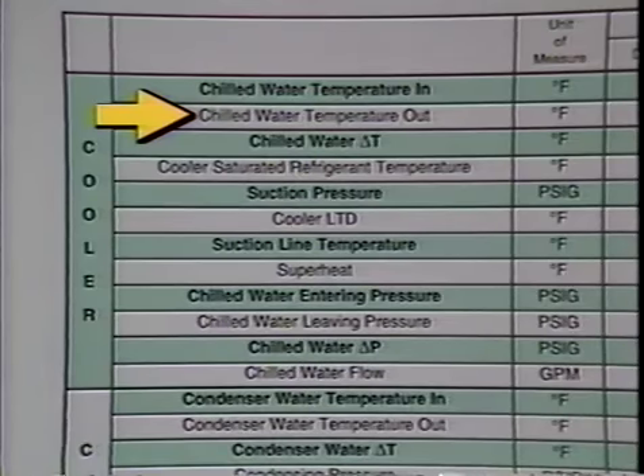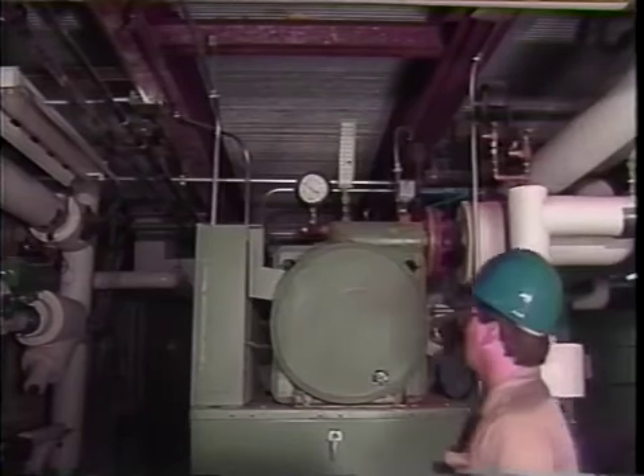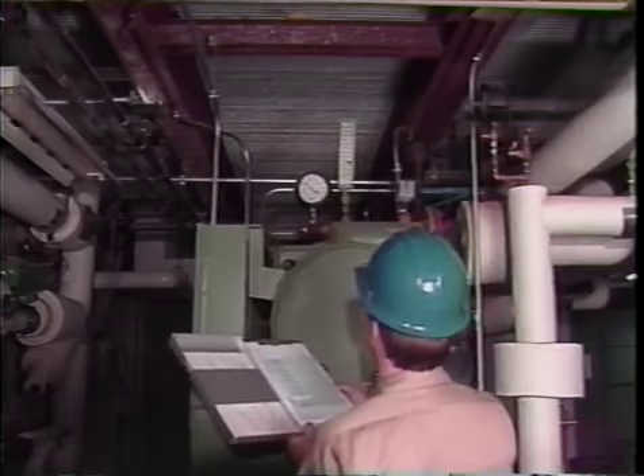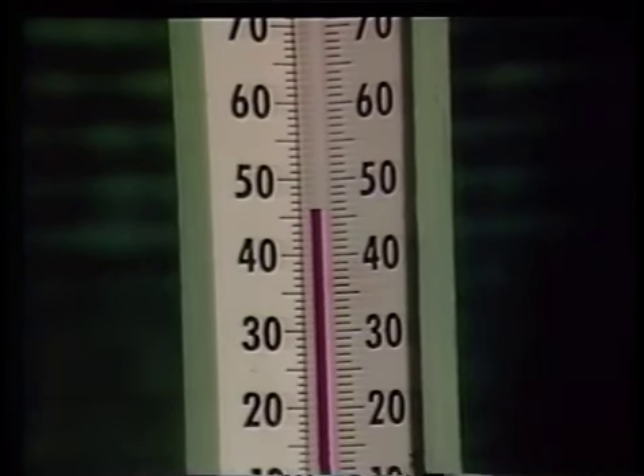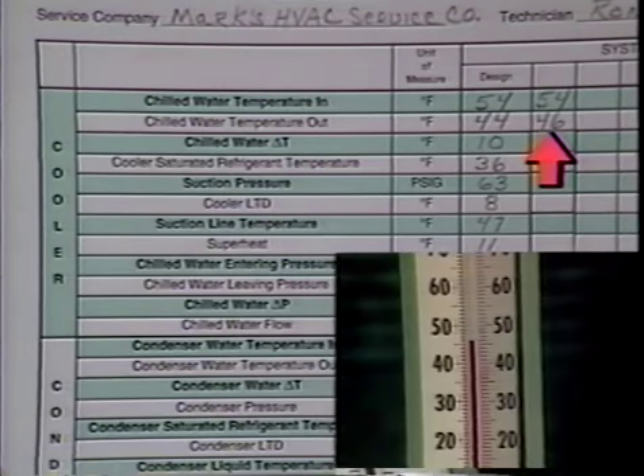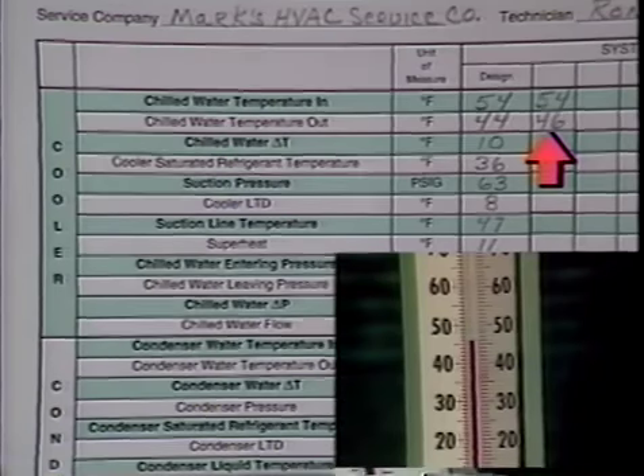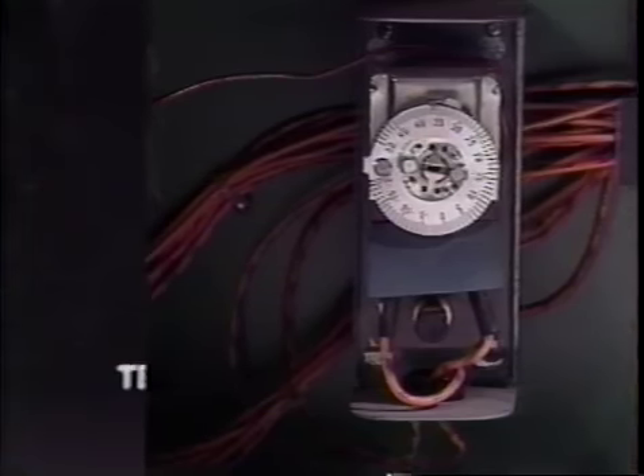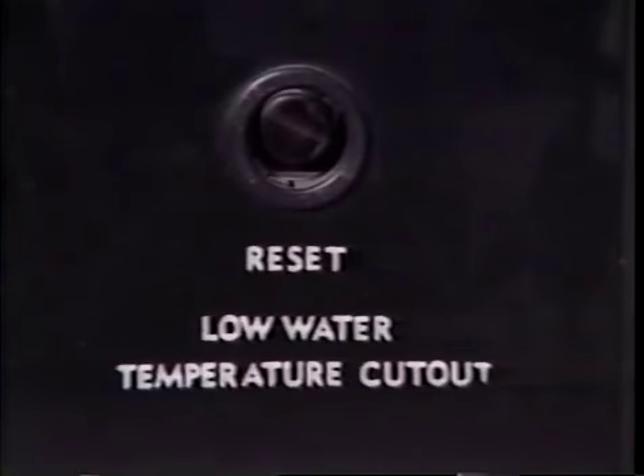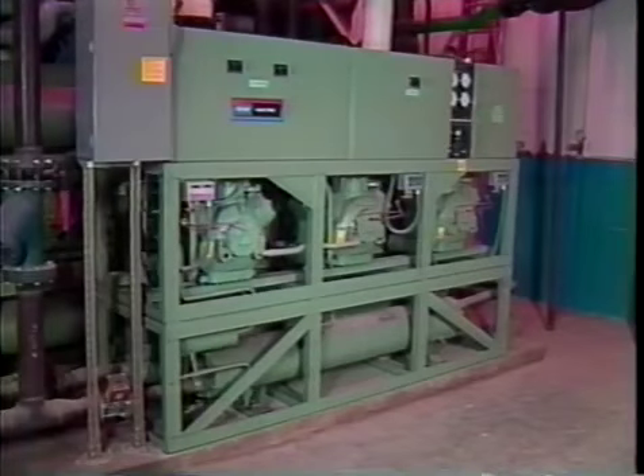Chilled water temperature leaving the cooler. We also need to record the chilled water temperature leaving the cooler. After the chiller is placed in operation, this temperature should be within plus or minus 1 degree Fahrenheit of the design leaving water temperature at full or part load conditions. Design leaving water temperature at full load is typically 44 degrees Fahrenheit. Under extreme light load operation, this temperature could drop below design leaving temperature. However, a control sensing the water temperature, low water temperature cutout recycle switch will shut the machine down. It's not economical or good operating practice to operate a chiller under extreme light load conditions if other means, such as outside air, will accomplish the cooling job.